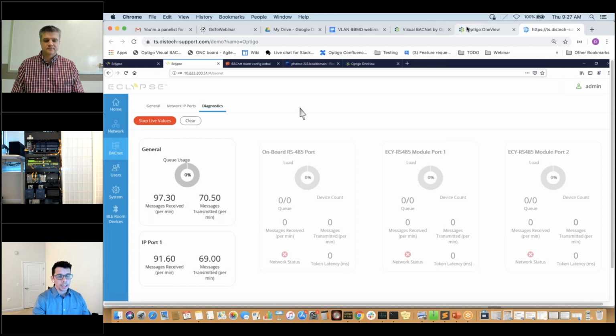Take advantage of it. But you would need to make it a foreign device or use a BBMD to accomplish that if you segregate those by VLAN. So keep that in mind. That's one of the things you have to look at in your design stage. Does this piece of equipment need to sit on a VLAN with other pieces of equipment? And just because it's in one room, don't let that deter you. If you have 4 controllers in one room and they all need to be on different VLANs, pull 4 Cat5 cables. It's more costly initially, but from a network performance standpoint, a configuration standpoint, and in the long run, a troubleshooting and stability standpoint, it's going to be far more cost effective.